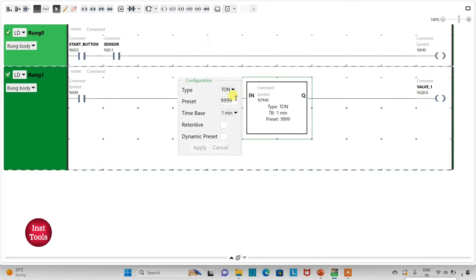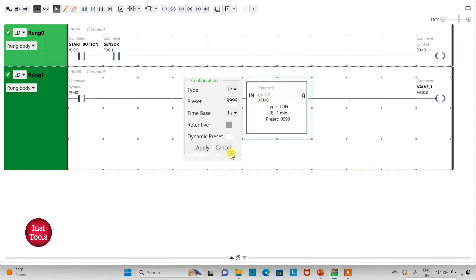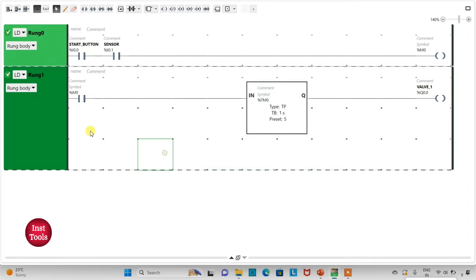Valve 1 should remain open for 5 seconds only, so I will insert a functional block TP pulse timer for valve 1. I will change the time base to 1 second and preset value to 5, then click Apply. When M0 gets activated, valve 1 will open for 5 seconds.